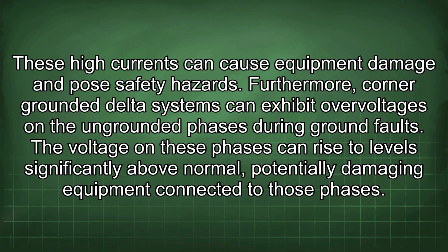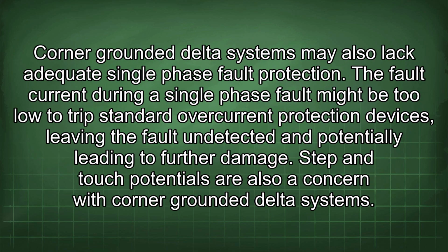The voltage on these phases can rise to levels significantly above normal, potentially damaging equipment connected to those phases. Corner-grounded delta systems may also lack adequate single-phase fault protection. The fault current during a single-phase fault might be too low to trip standard overcurrent protection devices, leaving the fault undetected and potentially leading to further damage.